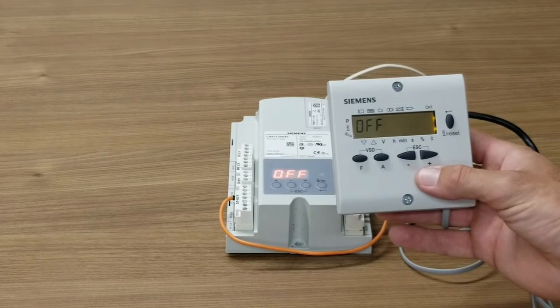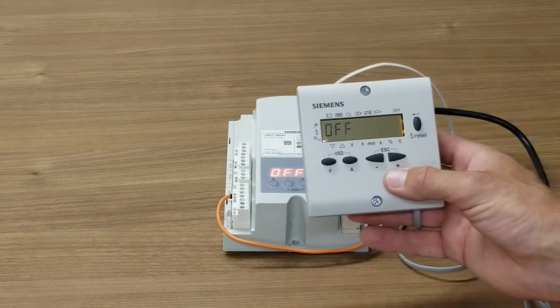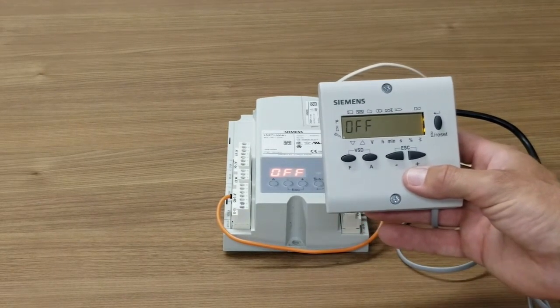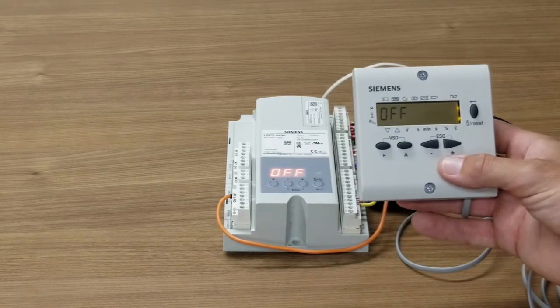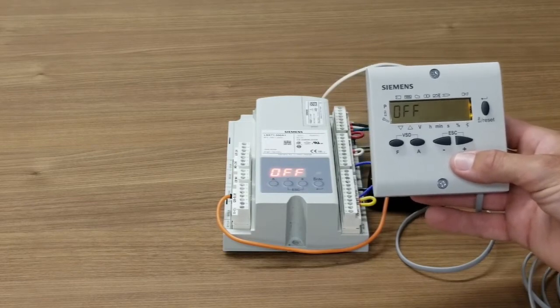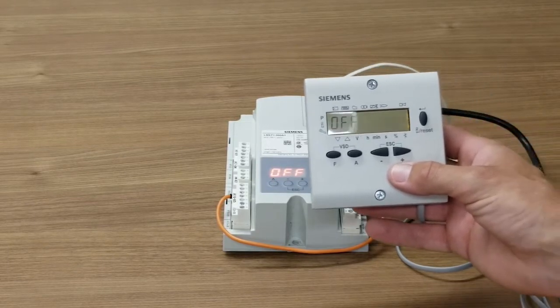For the purposes of this video, I'm simply going to demonstrate it on the LME-7, but know that logging into the LME-3 is exactly the same. A burner that is running will turn off upon logging in, so be sure not to make parameter changes if the burner cannot be shut down.